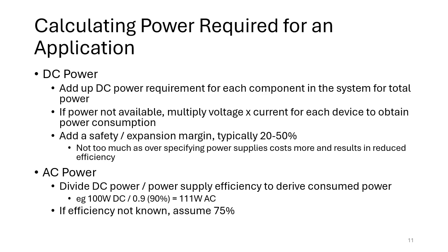It's important to add a safety or expansion margin, and typically this could be anything from 20 to 50%. You don't want to over specify too much, because having too big a power supply costs more and also means that you're running the power supply in an area where it reduces efficiency. But you'd certainly need some sort of safety margin, and possibly if you're going to be expanding in future. So if I needed a 3 amp power supply, I would probably round up to 4 amps or maybe even 5 amps. You might also need to consider inrush current as well.